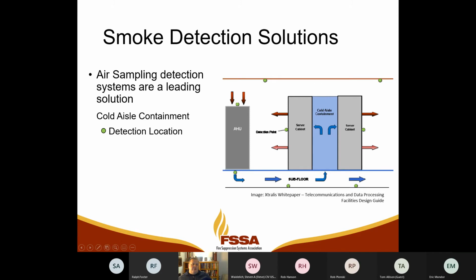David Quirk was a fire protection engineer for Verizon. He doesn't work for them anymore. But when all this was going on, he was the head fire protection guy for Verizon. They did some CFD modeling, and basically what they showed was that right at the top of a cold aisle system is dead air, and smoke's never going to go there. So it's a waste of money to put smoke detection at the top of a cold aisle.